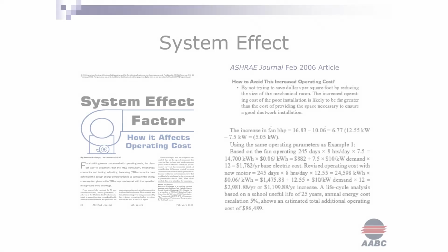So if a test and balance guy comes out there and his report does not show a number on the traverse and a note, but you guys are walking in the unit and it's a large enough unit that we could get in there and traverse, call them out on that. Tell them you expect that reading, because that's an important part of the process, especially from an energy management standpoint. All that conditioned air that we may not be accounting for, it's all a cost.